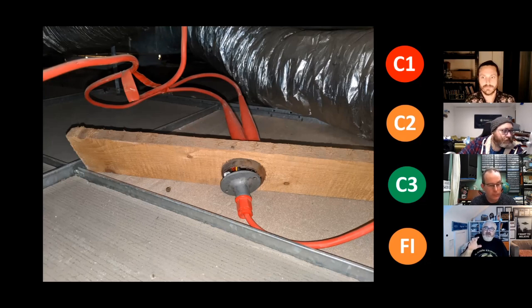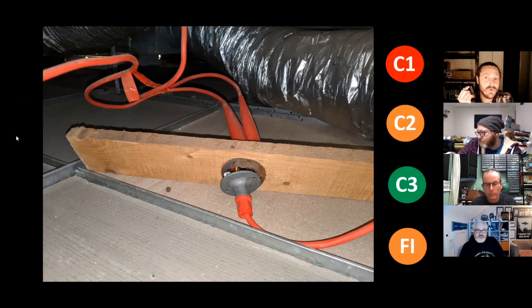More importantly, as a client, I don't want my contractors giving me a 7671 certificate going, there you go, it meets the regs. I want the contractor saying it doesn't just meet the regs, it has worked from the regs, and here's all the extra information we give because we want to do a proper service. I think 5839 part one is quite robust, to be honest. Everything in there is how a system needs to be installed, and the only time you change that is quite often a variation, because you cannot put a detector, for example, in a small room with an air conditioning unit, because it's going to blow the smoke and the hot air away. So it needs a lot of design consideration, but it's quite a robust document.